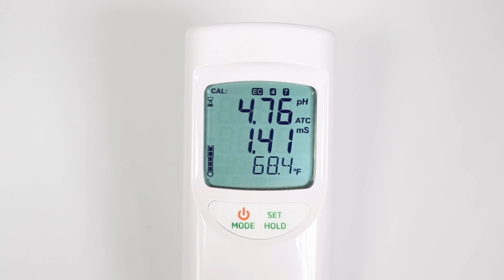EC/ppm calibration can be done less frequently than pH calibration with minimal drift over time. Calibrating every 1 to 2 months is recommended.